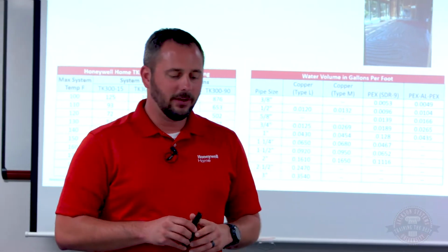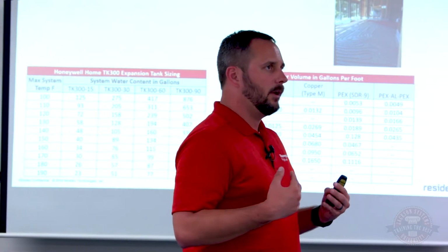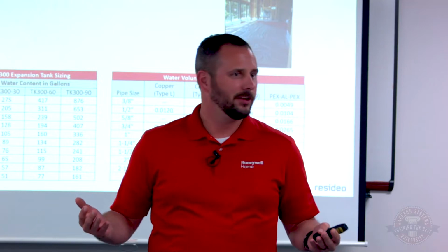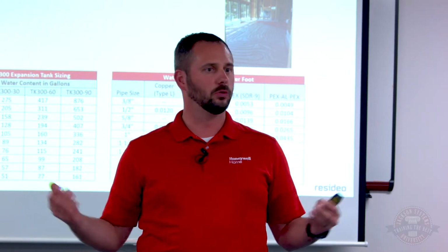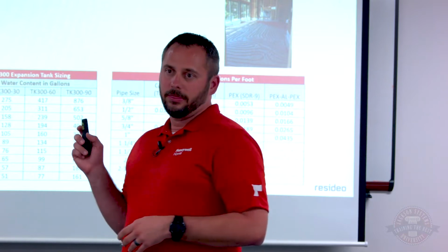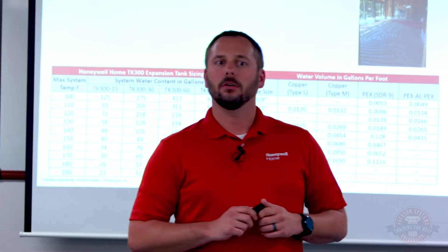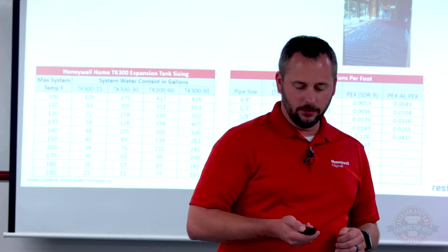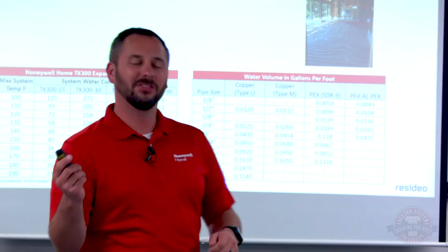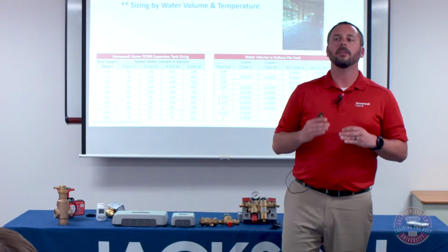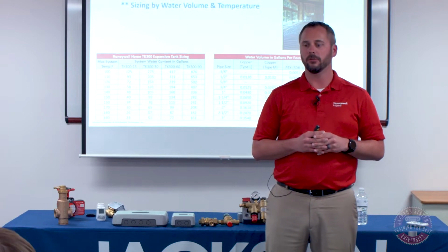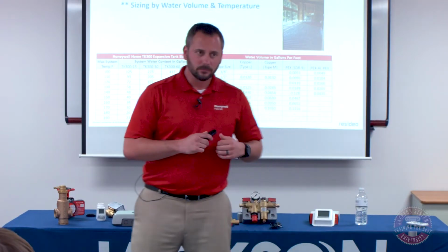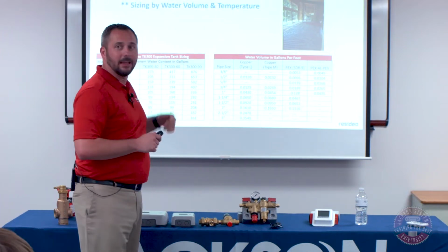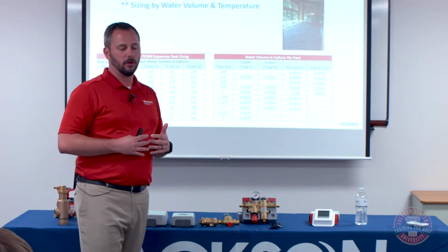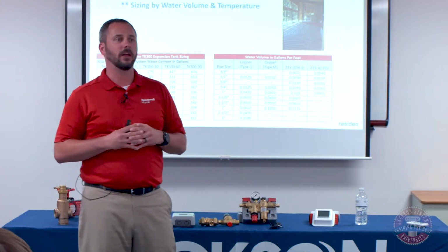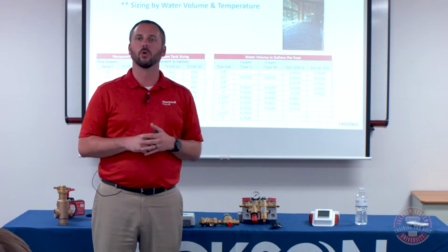So there's different expansion tanks out there, and how do you know which one to go with? Because we've got everything from a little 2-gallon all the way up to commercial floor-mounted expansion tanks. The way I recommend is by checking the water volume in your system and comparing that to the water volume capacity at varying temperatures in your system. So in this chart that I have here, I've got a couple of examples. On the left-hand side, what we're looking at is the acceptance volume of our common, call it residential, expansion tanks. We can get this for the bigger ones as well, but this is the majority of what we sell.